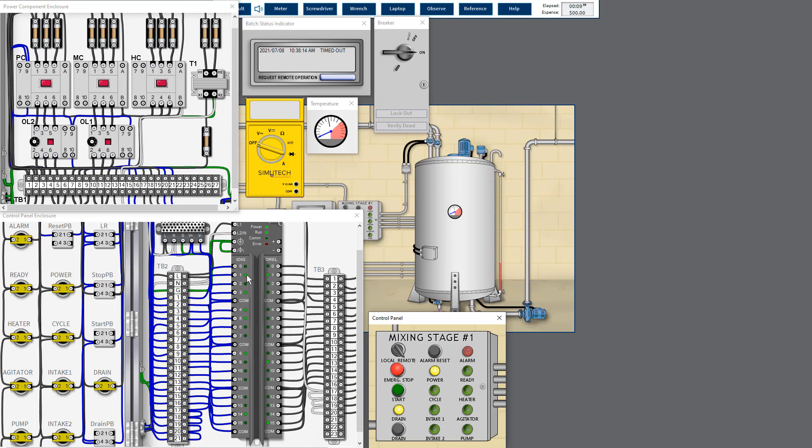So far I don't see any abnormality because the LED number one, three, four, five, fourteen from the PLC input channel loads and LED number one and two from the PLC output channel switch are usually energized under normal circumstances.